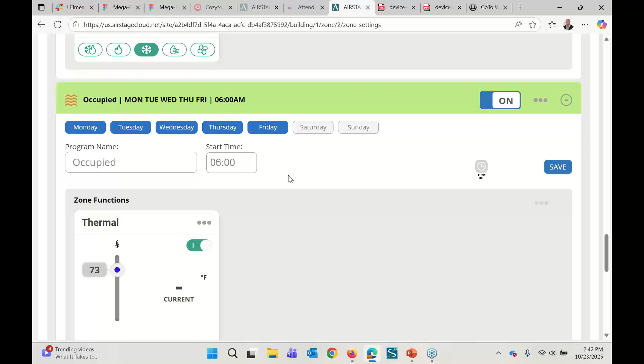Now, if you have somebody in a zone and that person uses their room controller, that will override the schedule. So if the space is occupied right now at 73 degrees, and they go to the room sensor or come up here and change that temperature to 78 degrees, it's going to stay at 78 until you get to the next scheduled event.